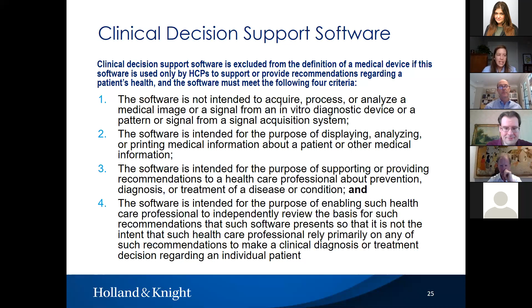So FDA has issued draft guidance on clinical decision support software. It's not even final guidance. It's been amended once. It's likely going to be amended again, but FDA breaks clinical decision support software into non-device clinical decision support software. So therefore it wouldn't meet the definition of a medical device because it meets all of the four criteria that we just laid out.